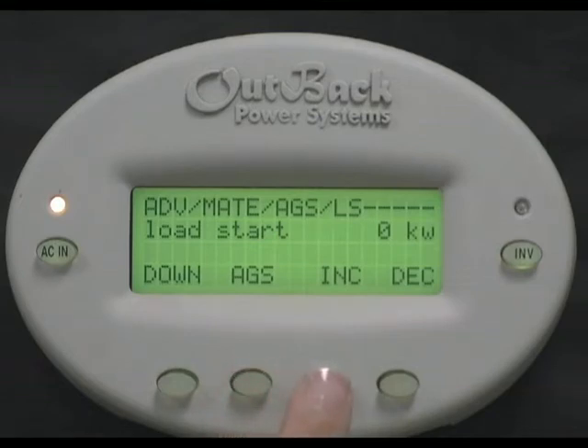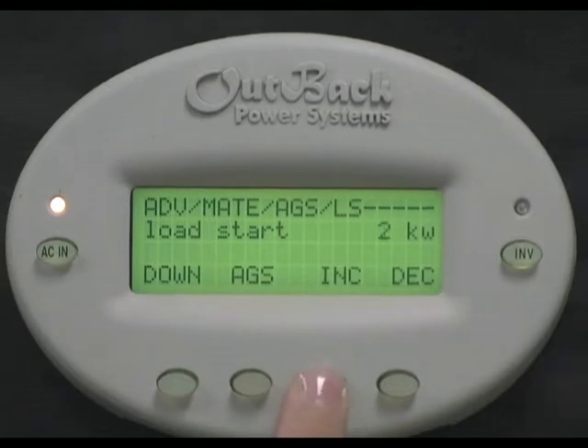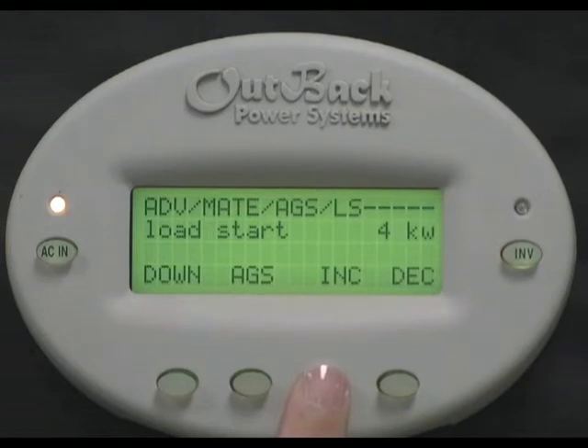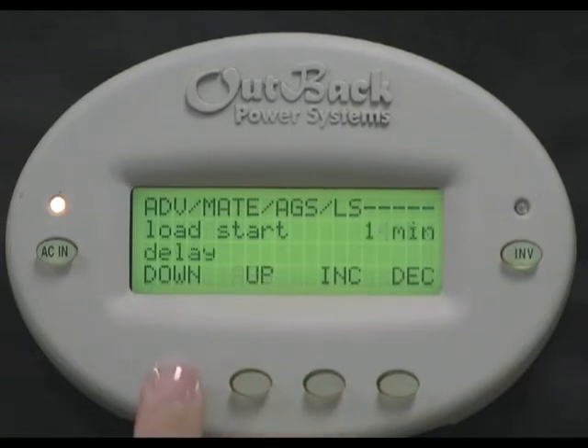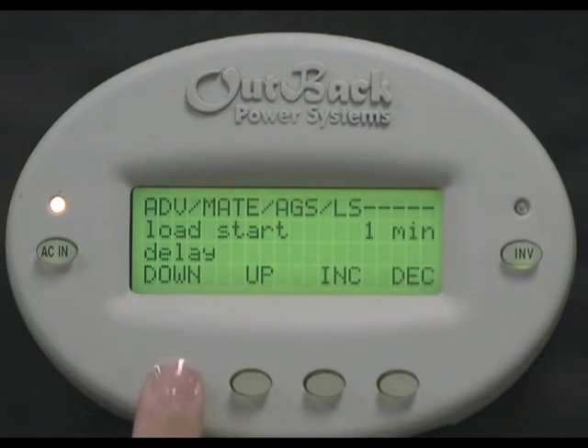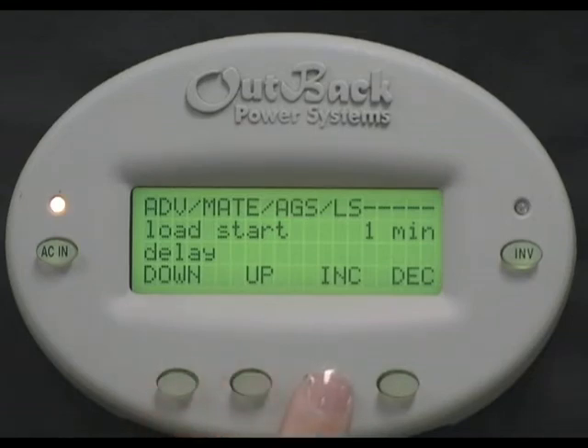Press increase to change the set point of when you want the generator to come on — in this example, 4kw. Load start delay is how long the load demand must be over that 4kw set point before the inverter will tell the generator to turn on. Press increase to change the set point. For our example, we'll leave it at one minute.